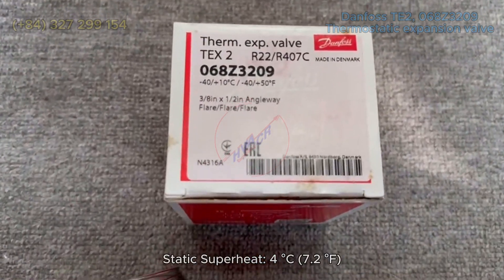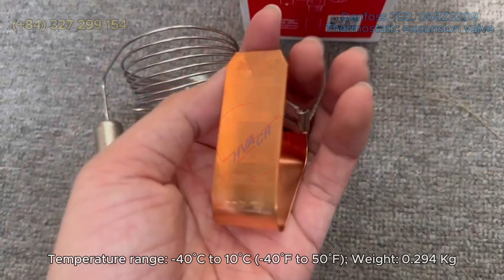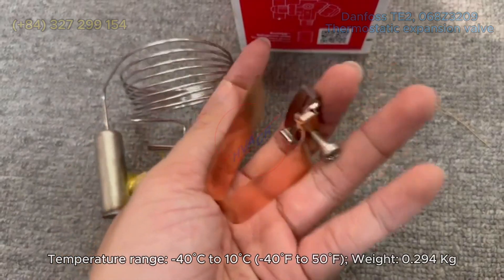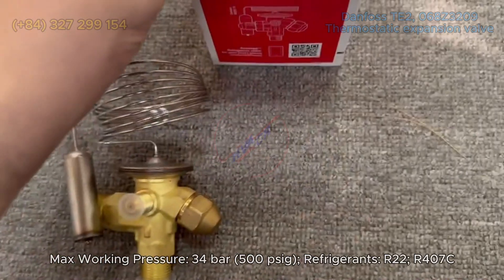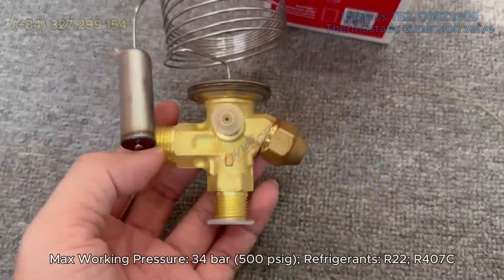Static superheat: 4°C (7.2°F). Temperature range: -40°C to 10°C (-40°F to 50°F). Weight: 0.294 kg. Max working pressure: 34 bar (500 PSIG). Compatible refrigerants: R22 and R407C.